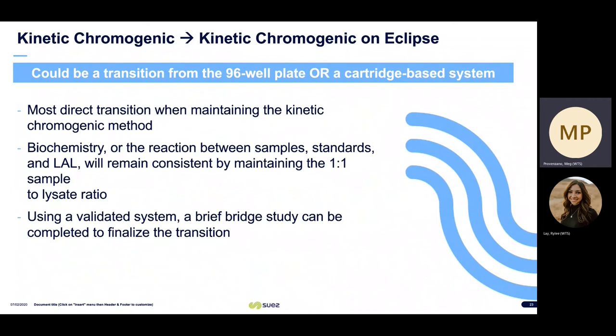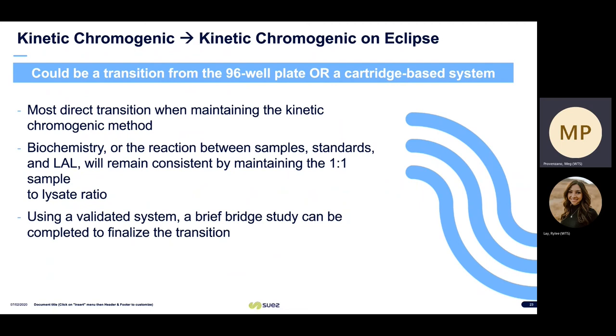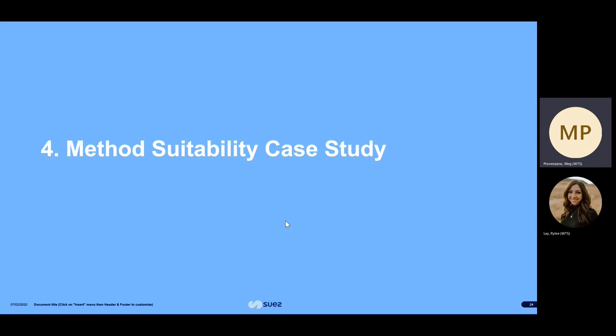The most simple of all is switching from a kinetic chromogenic method on traditional 96-well plates or a cartridge-based system to kinetic chromogenic on the Eclipse. This is the most direct transition when maintaining the kinetic chromogenic method. The biochemistry — the reaction between samples, standards, and LAL — will remain consistent by maintaining the one-to-one sample-to-lysate ratio. The ratio verification is part of the Eclipse system validation process, routine maintenance, and is a hard-coded protocol within the Eclipse software. Using a validated system, a brief bridge study can be completed to finalize the transition by performing side-by-side testing with the existing sample preparation, requiring little additional effort.